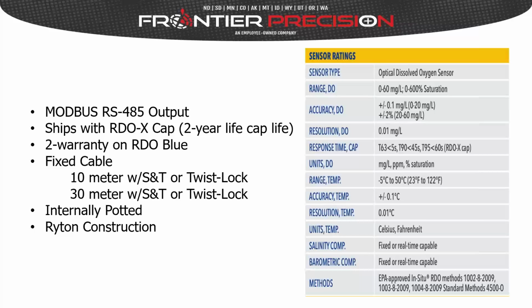So anyway, very good accuracy over the range of the sensor, the range being 0 to 60 milligrams per liter or 0 to 600% saturation. From 0 to 20 milligrams per liter, which is primarily where probably 90% of our customers are working, they're not getting up into the super saturation, we can give you plus or minus 0.1 milligrams per liter. This is usually better than twice the accuracy of the old Clark cells, the polarographic sensors. And the response time of these sensors is typically twice as fast as the old polarographic or Clark cell technology. And then down at the very bottom, you can see the EPA-approved methodology by EPA number, referencing the standard methods.